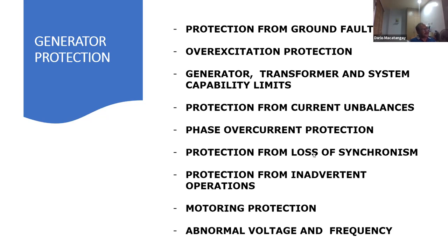Protection from inadvertent operation. For example, this is like inadvertent energization. Say you're doing maintenance on the generator, and suddenly someone closes the breaker, so the system powers the generator from an idle condition. That will be like running the generator as a motor. When a motor starts, the starting current is almost 6 times the full current. So if you suddenly energize a generator from standstill, there is no magnetic field, and you can damage the generator.